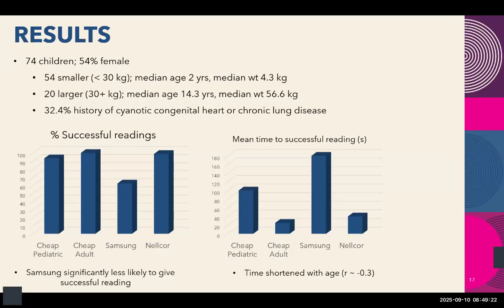The cheap pediatric one, close. The Samsung had a lot of trouble. It only got successful readings in about 60% of people. In terms of how long it took to get a reading, the Nellcor did it in about 30 seconds. The cheap pediatric one took much longer, about 100 seconds. The cheap adult one was quick, it was about 20 seconds. And the Samsung took ages. It took up to 3 minutes to get a successful reading.